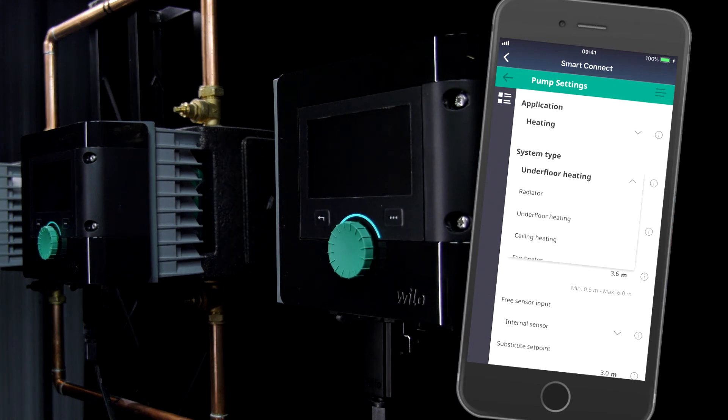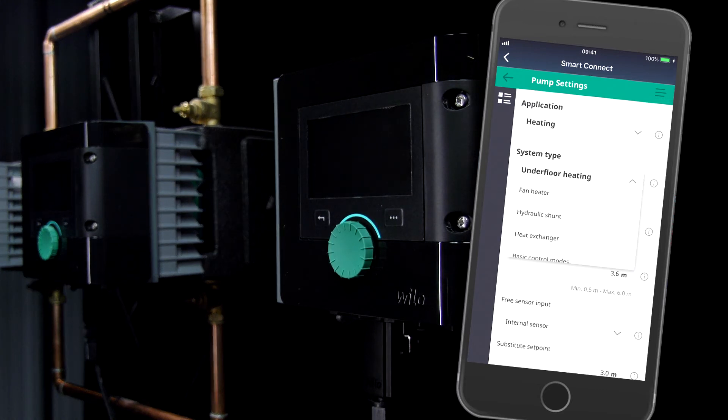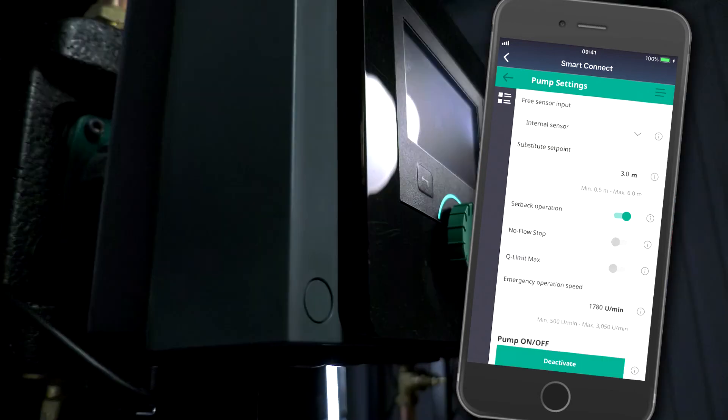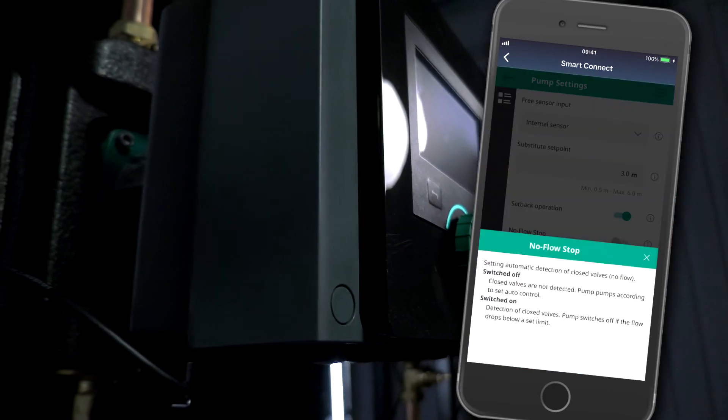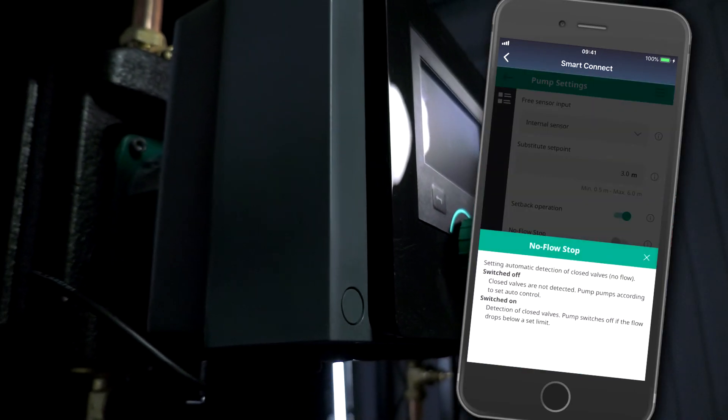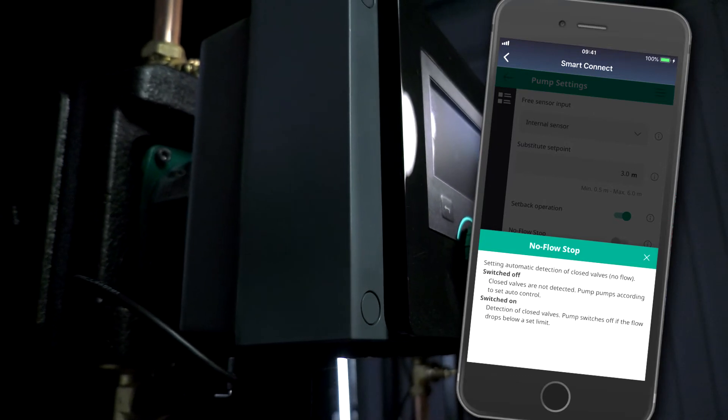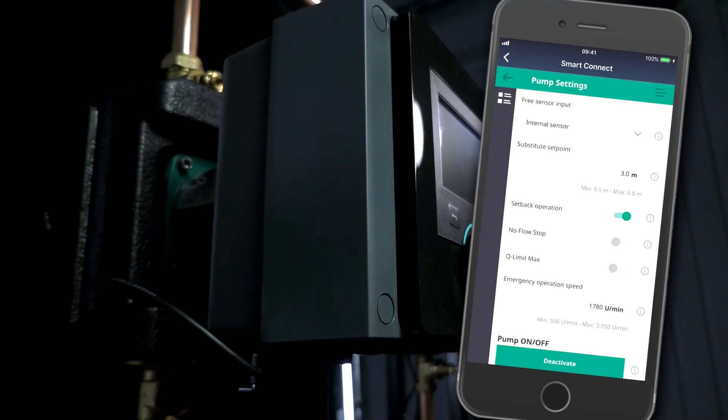We can have a look at the different types of control mode we've got and we can add additional functions like the no flow stop function. So say there's a problem with all the radiator TRVs in a house and there's just no flow, the pump will recognize that and switch itself off.